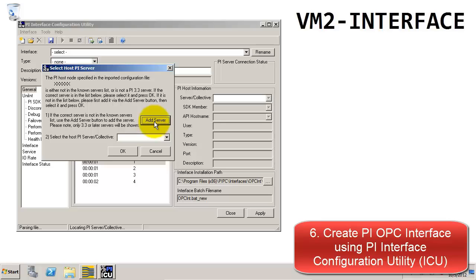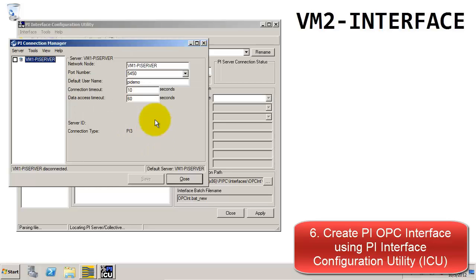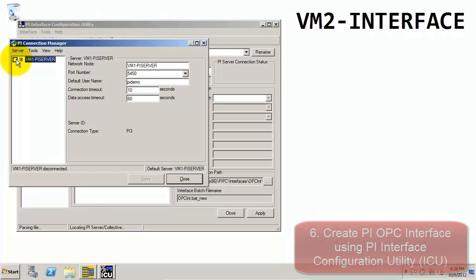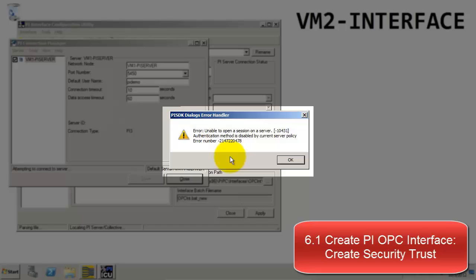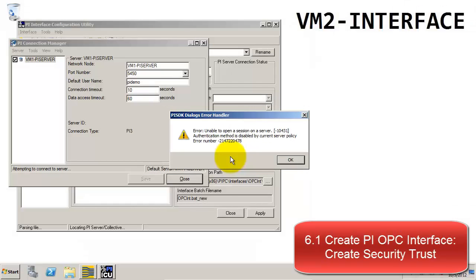Now we're going to choose the PI server. If you click Add Server, we see the VM1 PI server. If we try to connect, you'll notice we get an error: unable to open a session on a server. This is because we don't have the appropriate trust mappings in place for this connection, so this is something we need to take care of now so we can continue the OPC interface configuration.